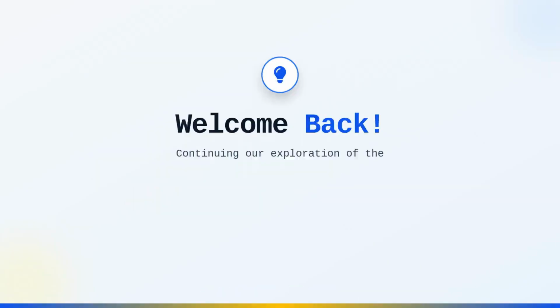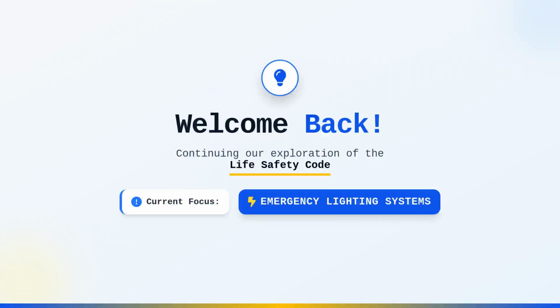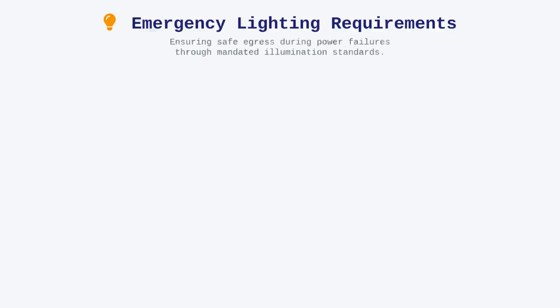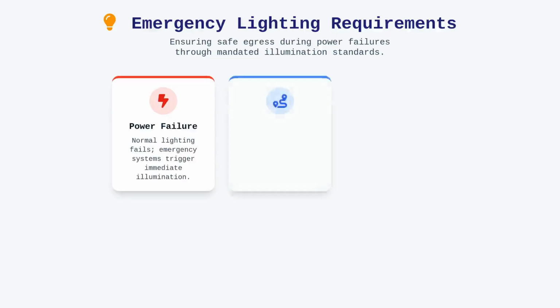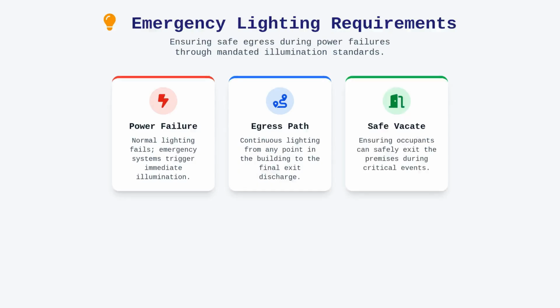Welcome back to our exploration of the Life Safety Code, where we now focus on the essential requirements for emergency lighting systems. Emergency lighting is not merely a convenience, but a fundamental life safety component designed to ensure that occupants can vacate a building during an electrical power failure. When normal lighting fails, the system must provide immediate illumination along the entire egress path, starting from any point within the building and continuing to the point of exit discharge.